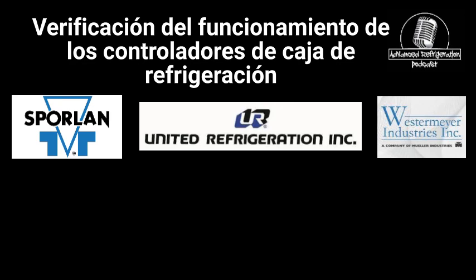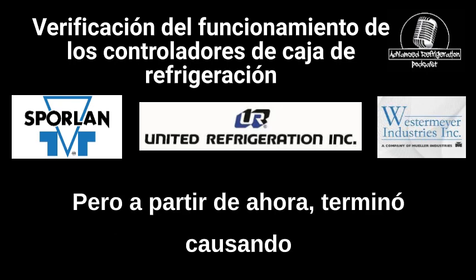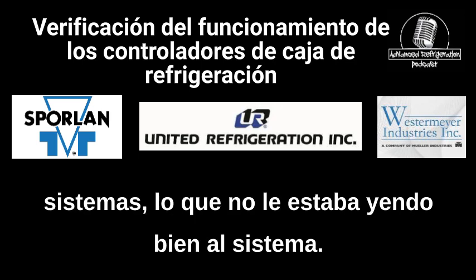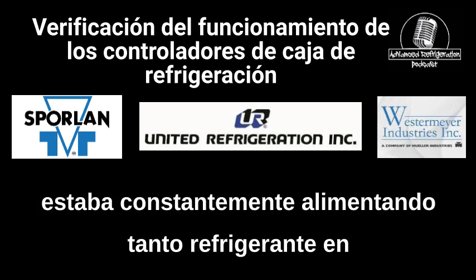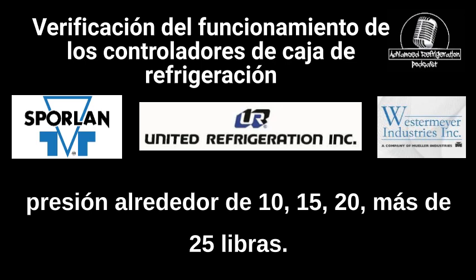So I've got to reach out to the manufacturer and see if they have a fix for it. But as of right now, it ended up causing us to have intermittent flooding on a lot of the systems, which was not doing well for the system. It was causing a lot of spikes on the rest of the circuits, because it was feeding so much refrigerant into some of these lines that it was backing up pressure about 10, 15, 20, upwards of 25 pounds.